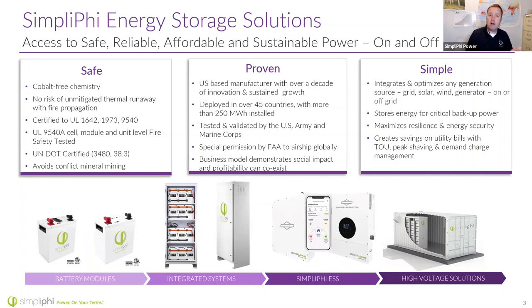Like low battery cutout voltages, the floats, the absorb voltages. And what we have online are a lot of integration guides that allow you to look up one of these guides, and it will tell you, in the order that the equipment is asking for those set points, all the exact set points, so that you know you're programming that system properly.